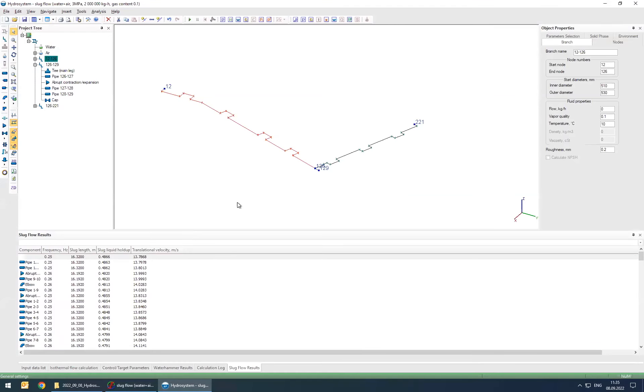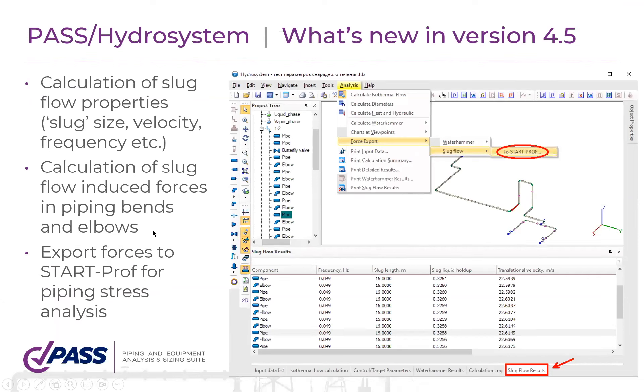I'll be honest: I selected special parameters for the slug flow so the problem would be visually clear. But these parameters are not synthetic or fictional — they are absolutely real. This is what can happen if you have slug flow inside your piping system. The problem can be crucial, and using both HydroSystem and StartPro together, it takes only five to seven minutes to understand whether you have a problem or not. If you're dealing with two-phase flow analysis, be sure to analyze slug flow using these two tools combined.